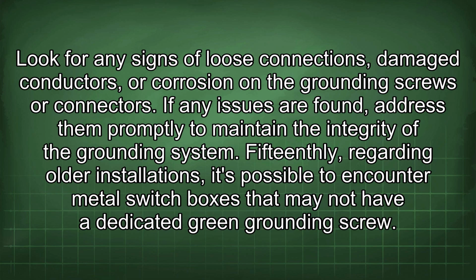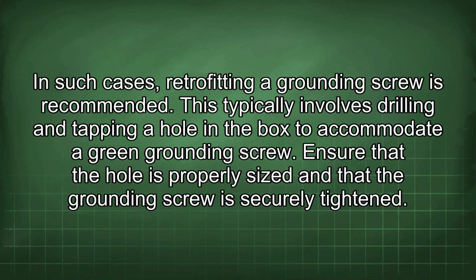15thly, regarding older installations, it's possible to encounter metal switch boxes that may not have a dedicated green grounding screw. In such cases, retrofitting a grounding screw is recommended. This typically involves drilling and tapping a hole in the box to accommodate a green grounding screw. Ensure that the hole is properly sized and that the grounding screw is securely tightened.